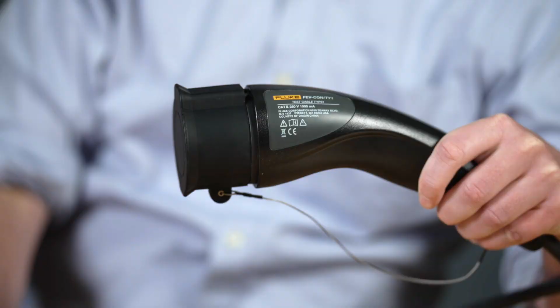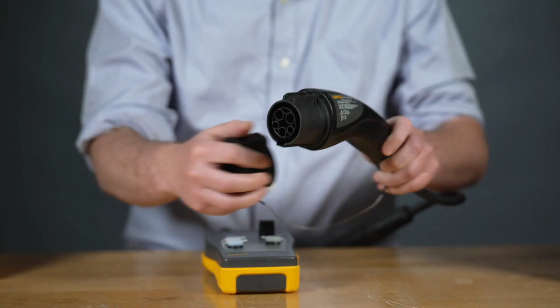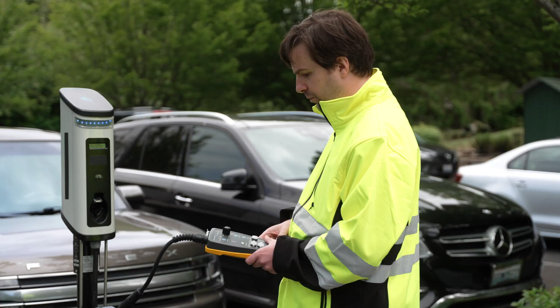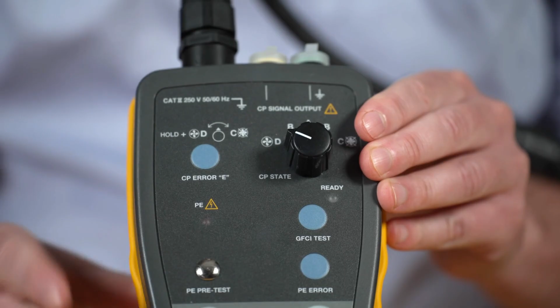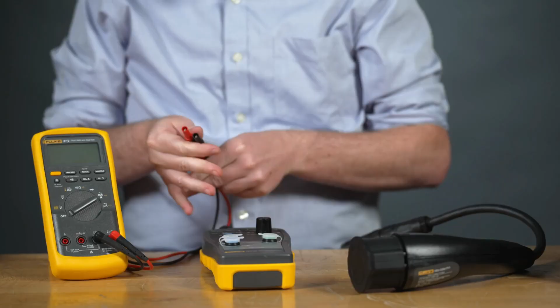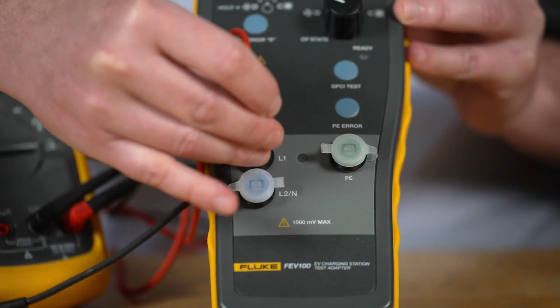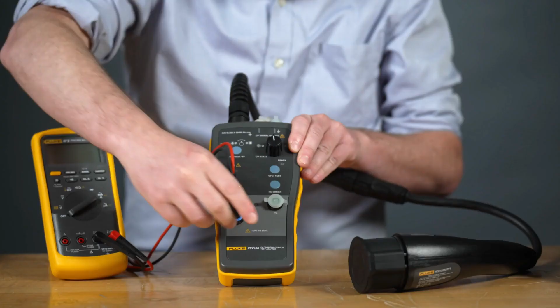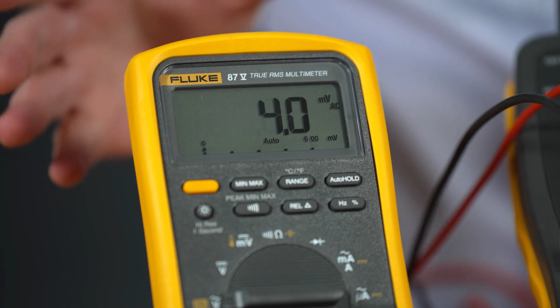The Fluke FEV 100 connector accessory is your interface for Type 1 socket outlets or J-plugs on a Level 2 charging station. Let's see how it works. First, connect the FEV 100 station test adapter to the charger's Type 1 connector and check that the station is correctly wired and secure. Make sure that protective earth is functioning properly using the PE pre-test safety feature. Then connect the multimeter—it's recommended to use a Fluke 87V. Check the output voltage and measure the continuity of the PE connector.